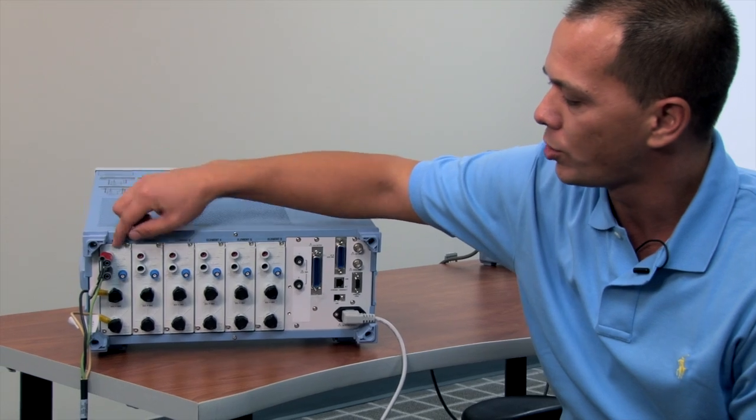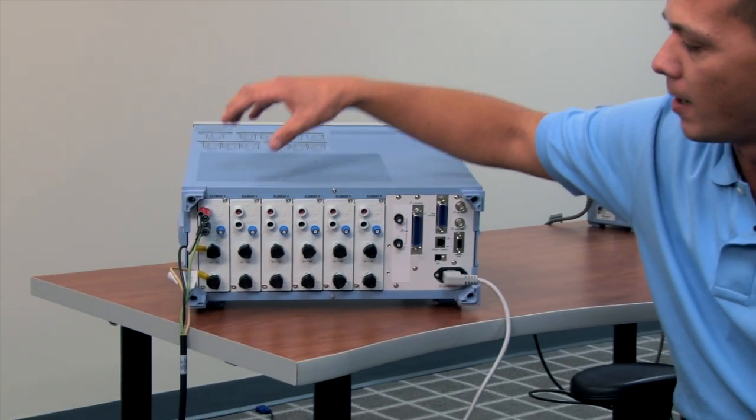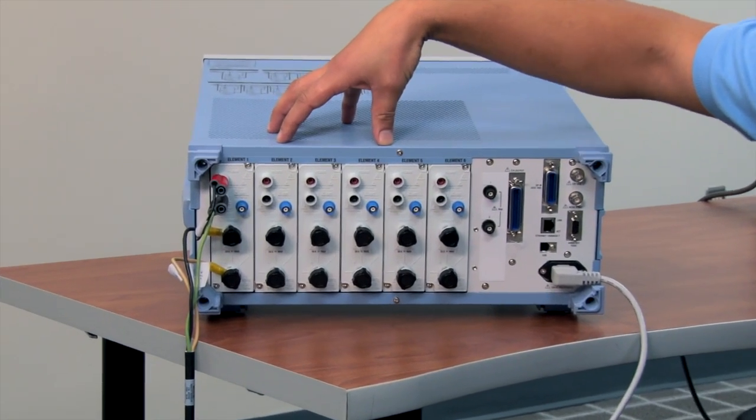We have direct voltage and current inputs. There's two input elements to choose from, one with a 5 amp maximum and one with a 50 amp maximum, both rated at 1 megahertz frequency.